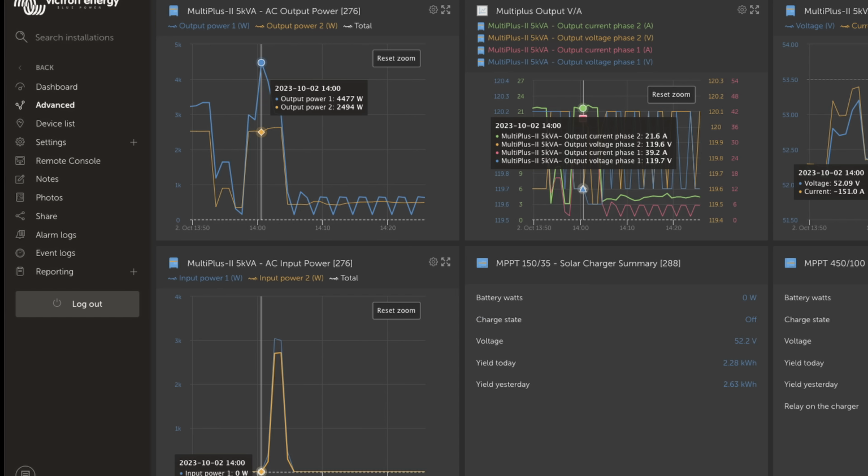The water heater's going, the well's running, the dishwasher, the microwave, and then I think she turned a mixer on. And that pushed one phase over that limit. And so it ran until it dropped down below that 1,300 watts, and then it switched back over. Seamless switch. No light blinking, no nothing.